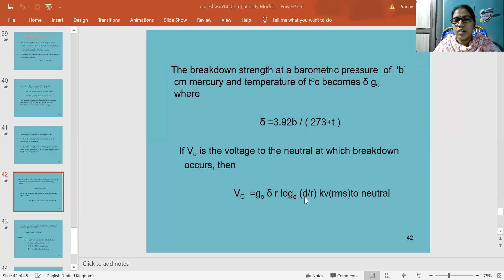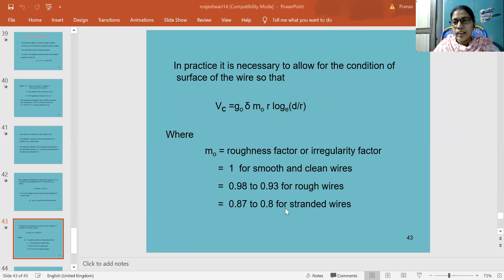And in practice, it is necessary to allow for the condition of the surface of the wire, so that Vc is equal to g naught delta m naught r log of d by r, where m naught is the roughness factor or irregularity factor. This is 1 for smooth and clean wires, 0.98 to 0.93 for rough wires, and 0.87 to 0.8 for stranded wires. And small g is the maximum potential gradient or breakdown value of air, which is equal to 30 kV maximum per centimeter or 21.2 kilovolts RMS per centimeter.